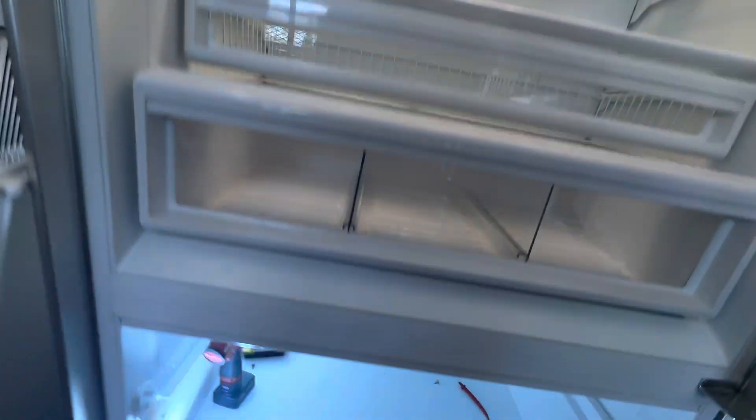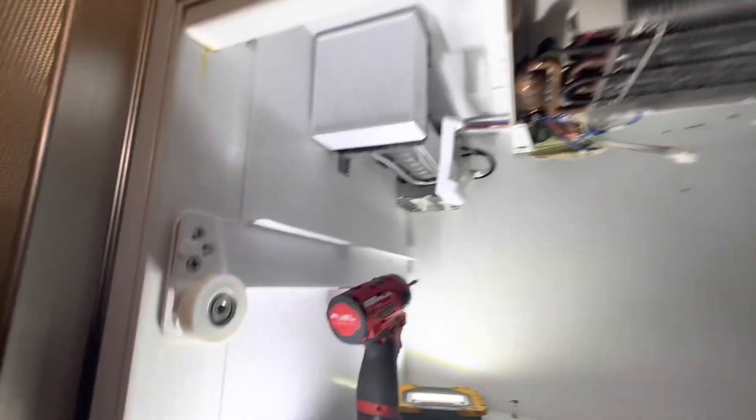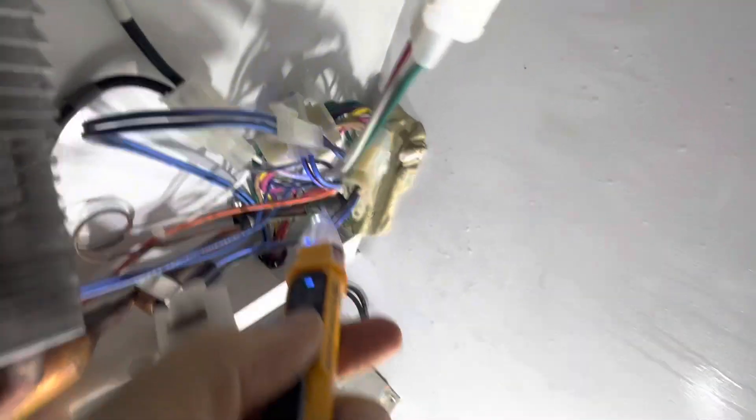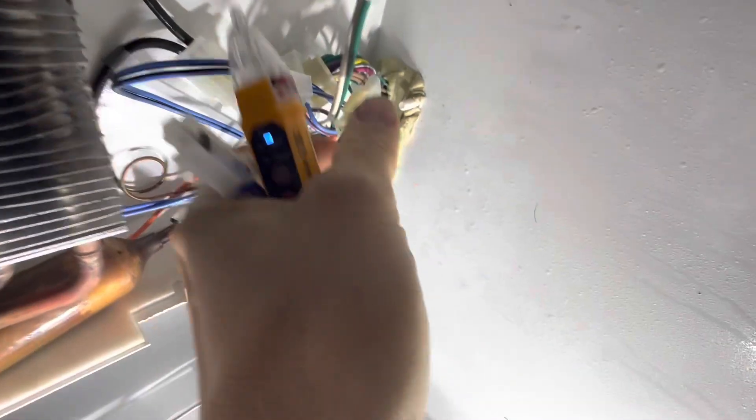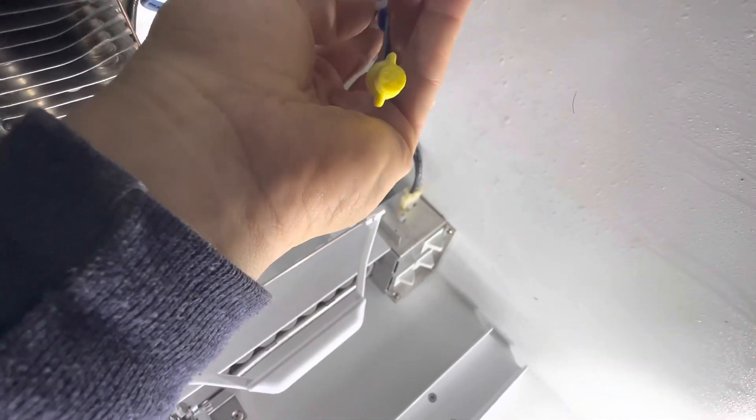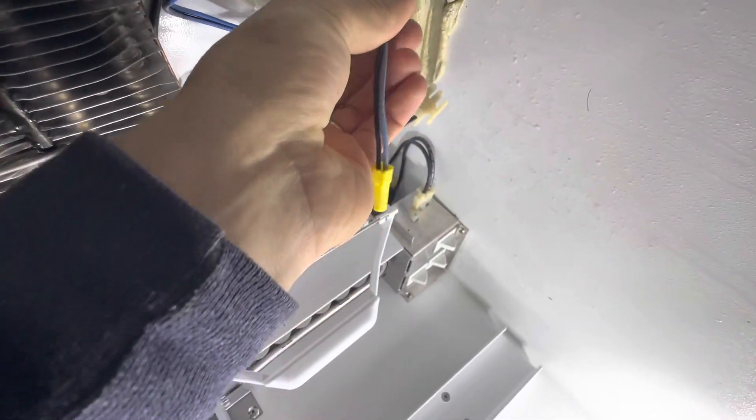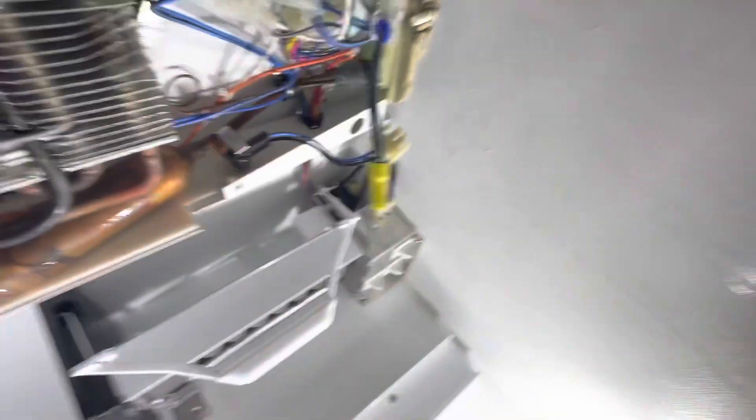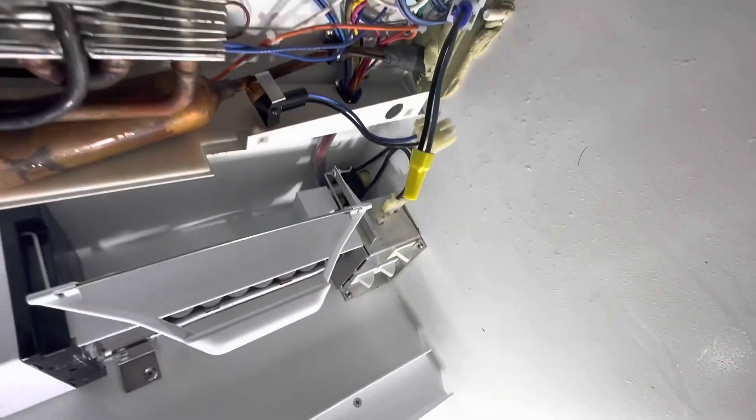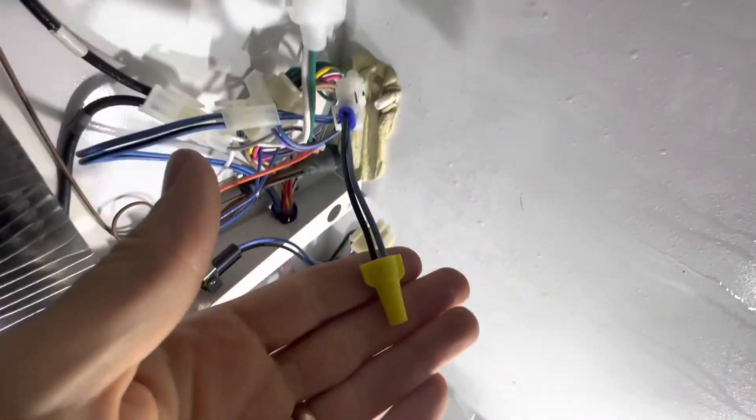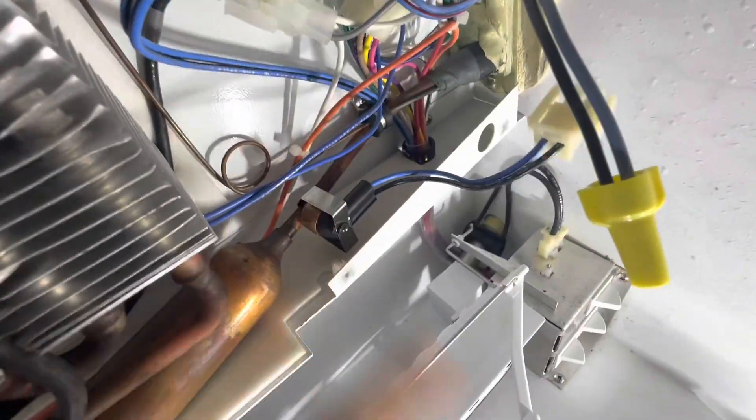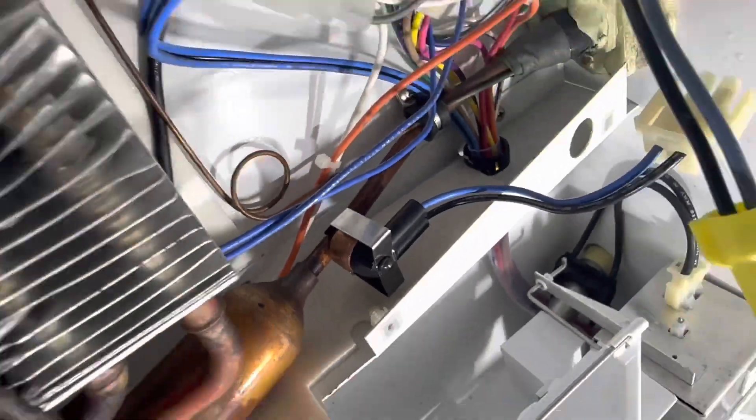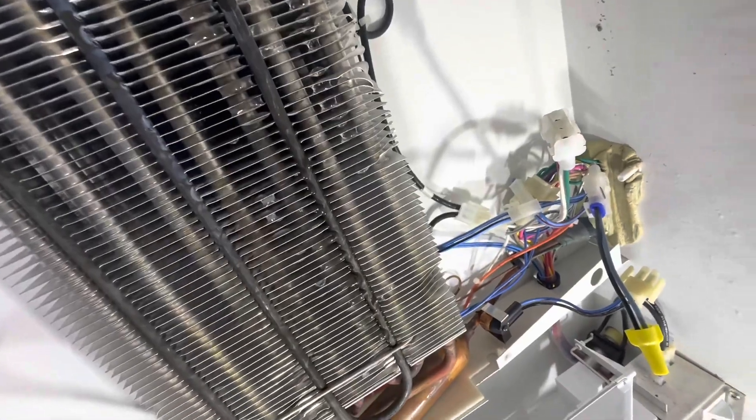Now I put it into defrost and what we are going to do is go down and take a look at our terminator switch, which has power but does not allow power through to the heaters. So I'm going to unclip that and I'm going to clip in my jumped out terminator switch, which will be permanently closed, allowing power through to the heaters. Let's go ahead and click that in and now we have power at the heaters now. So that confirms it. I'll hear those heaters come on and get hot, and our terminator switch is the problem. I'll reinstall a new terminator switch and mount it properly on the low side of the coil, and that will fix our defrost in this scenario.